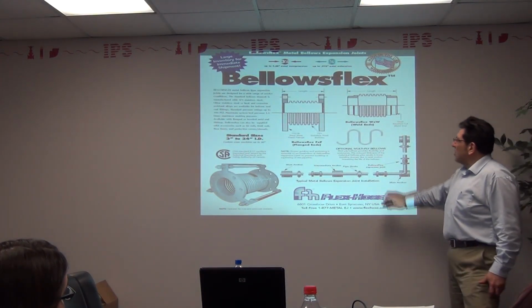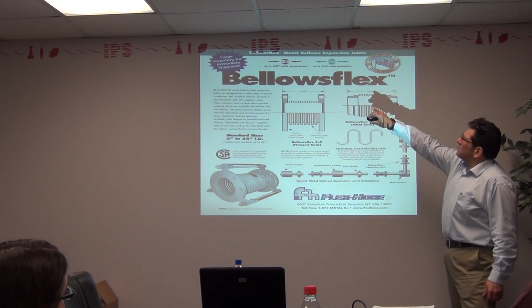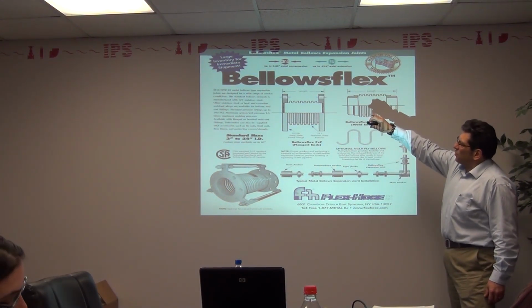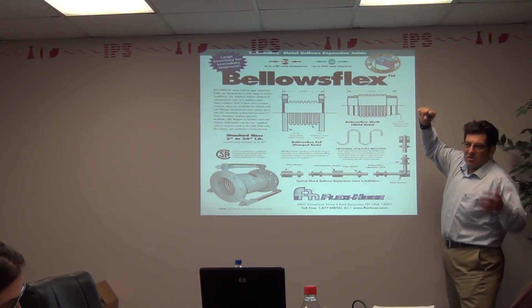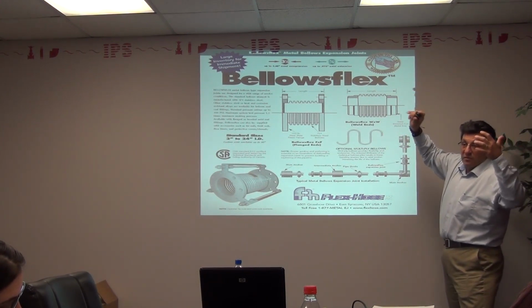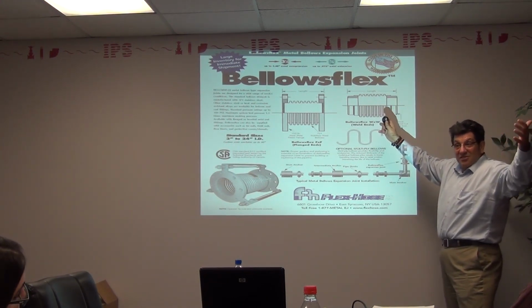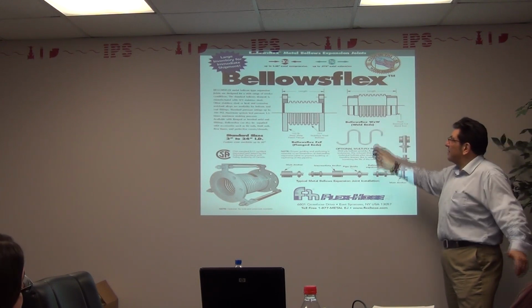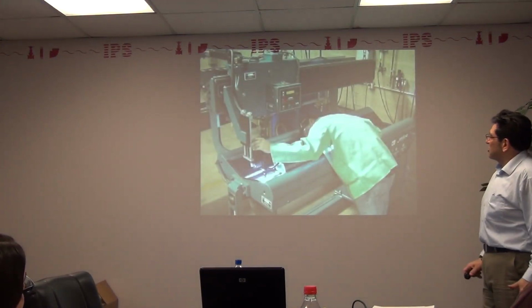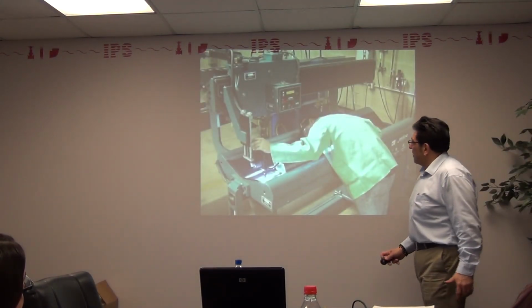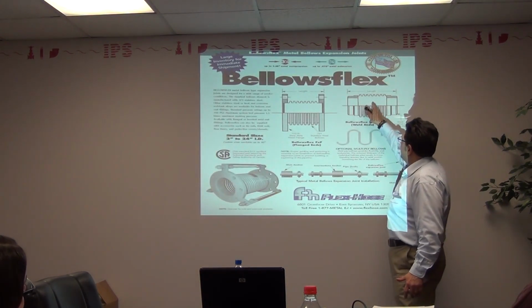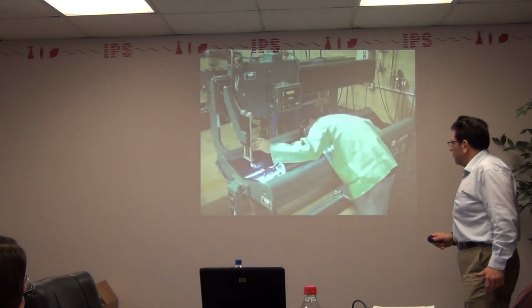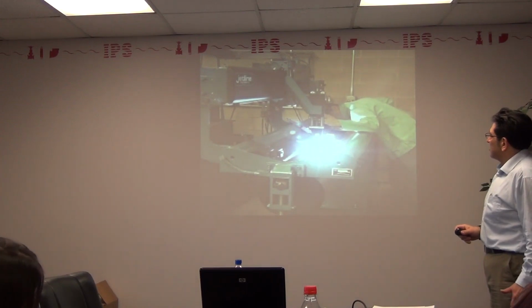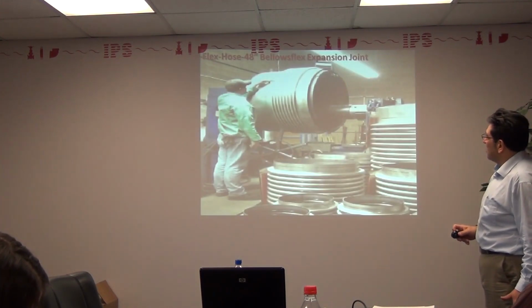Bellows Flex, these are all custom. You're only really going to get up to a little over 3 inches with one of these, whereas with the Flex Press you can do 8 inches on one of them. If you do a dual, you can do 16 inches of expansion. But again, we'll help you design it. It's our seam welder that actually welds this capsule itself when it's in its rolled form. You can see it's all back purged, and the heat-affected zone becomes very small and very light.